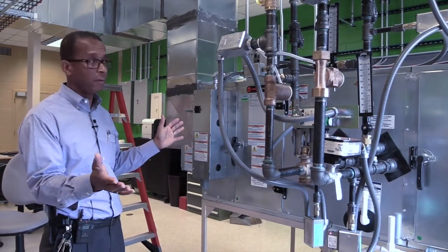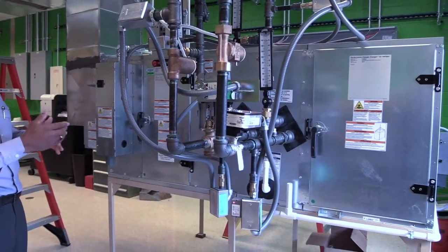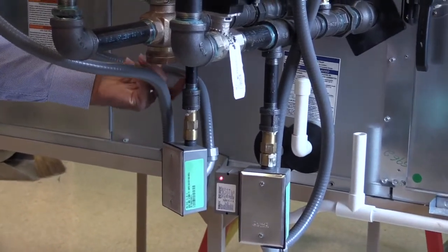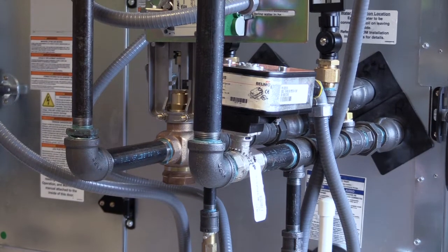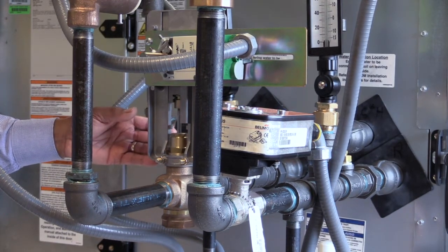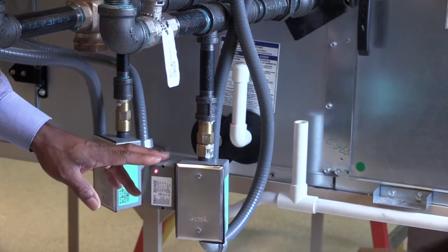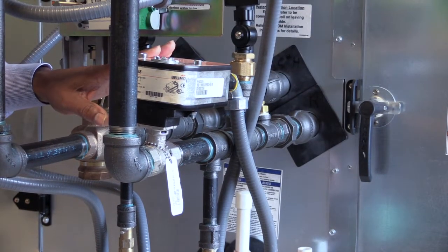In this section of our lab, we have our air handling unit, which consists of a belt-driven fan, a chilled water coil, and a hot water coil. A temperature thermistor in a well senses the temperature of our chilled water and sends a signal back to our main building controller. Based on the set point, the controller can modulate the valve to allow more or less chilled water into the coil. Similarly, a thermistor senses the hot water supply temperature to modulate that actuator as well.